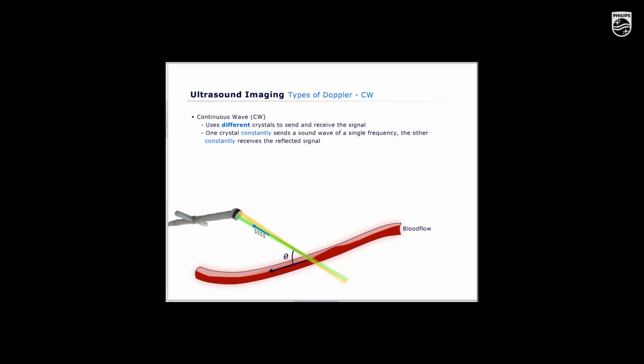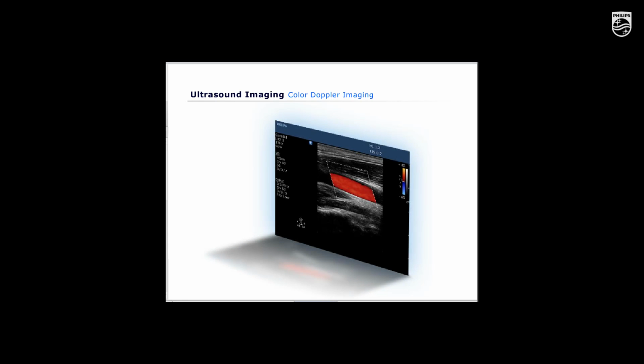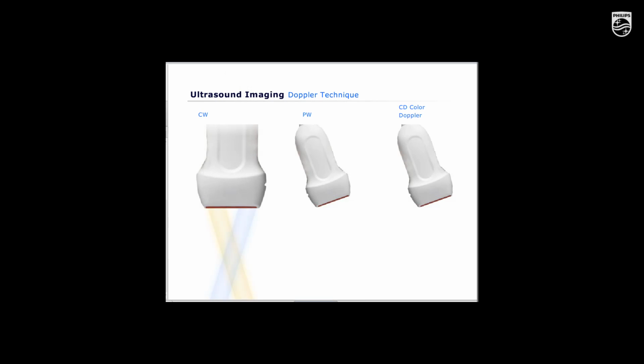Continuous wave uses different crystals to send and receive the signal. One crystal constantly sends a sound wave of a single frequency, while the other constantly receives the reflected signal. Color Doppler imaging represents blood flow in an ultrasound image and shows how to determine the direction. CW will send and receive constantly. This technique uses two different sets of elements on one transducer. PW sends a burst of waves and then waits for the returning echoes. This technique uses the same elements for sending and receiving. CD color is the same as the PW technique, but repeats many more times.